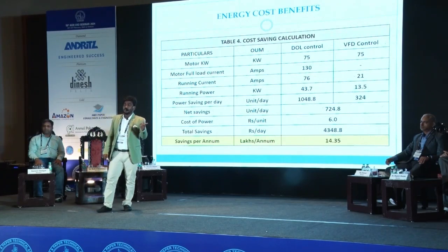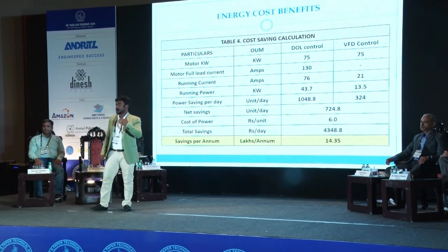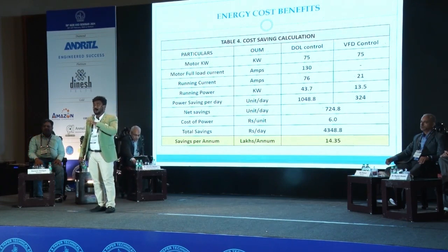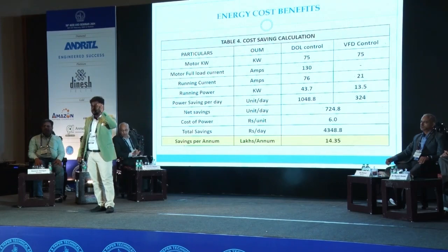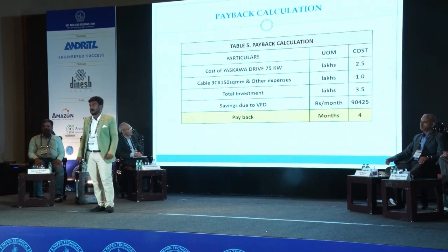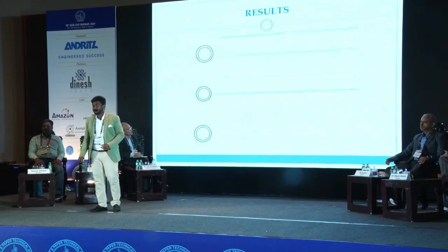And the control valve, which was operating at 30 to 45% opening, increased up to 80 to 85% to maintain the required hydromix level. There was no disturbance in the process. Everything was working seamlessly, and we reduced the power consumption from 76 amps to 21 amps. That gives us around 14 lakhs per annum savings. For the VFD installation, we invested around 3.5 lakhs, which could be recovered in 4 months by the savings due to the VFD.